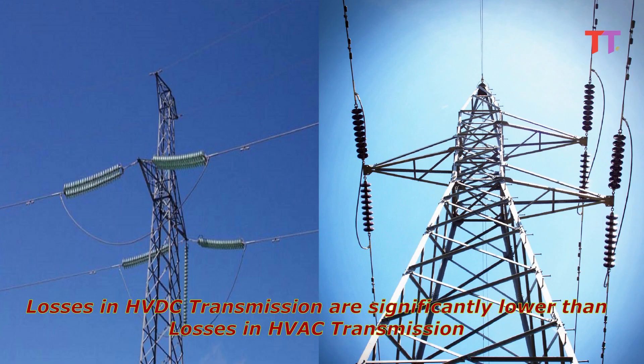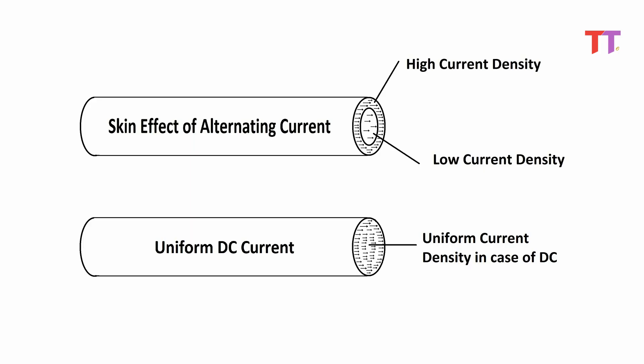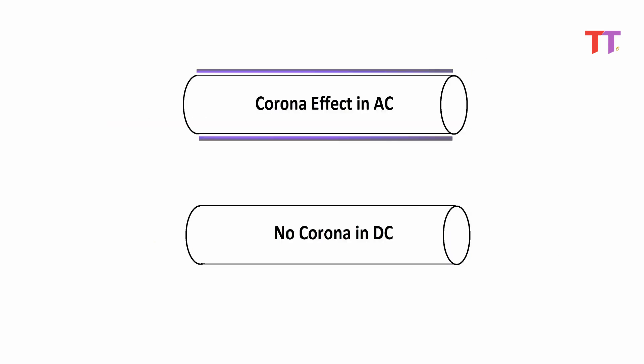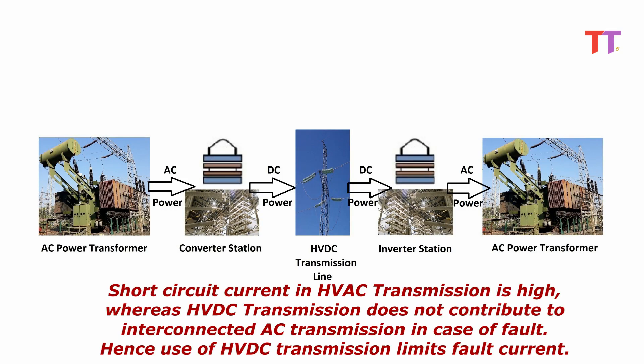Losses: Losses in HVDC transmission are significantly lower than losses in HVAC transmission. Skin effect is completely absent in HVDC transmission, and Corona losses are also lower in HVDC. Short circuit current: Short circuit current in HVAC transmission is high, whereas HVDC transmission does not contribute to interconnected AC transmission in case of a fault. Hence use of HVDC transmission limits fault current.